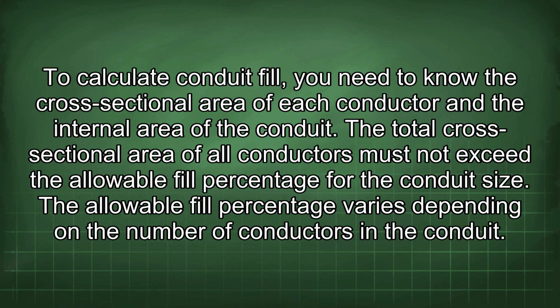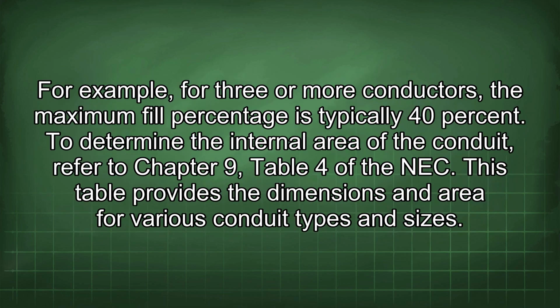To calculate conduit fill, you need to know the cross-sectional area of each conductor and the internal area of the conduit. The total cross-sectional area of all conductors must not exceed the allowable fill percentage for the conduit size. The allowable fill percentage varies depending on the number of conductors in the conduit. For example, for 3 or more conductors, the maximum fill percentage is typically 40%.